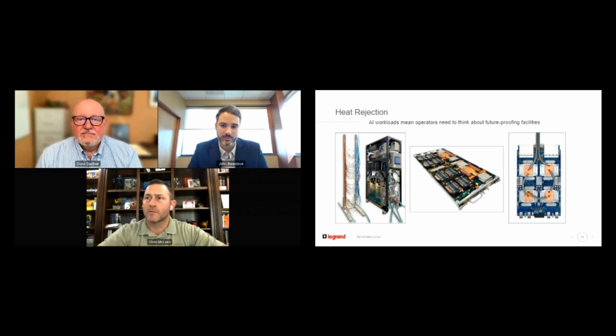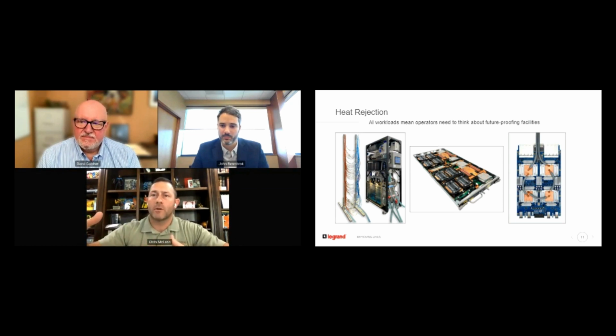I can see in the comments somebody asks about air cooling these higher density racks. Absolutely possible to do it with air. To be honest with you, we have done 60 kW racks with air. The change here is on the construction side. Folks think about these as $500 a square foot, $1,000 a square foot facilities, and 60 to 80% of the cost is typically electrical. That's not changing. The whole total cost is going up, but you're still at, say, 60% or maybe a little bit less of that total cost being electrical.